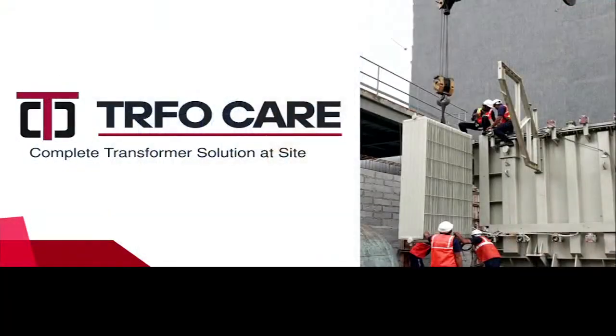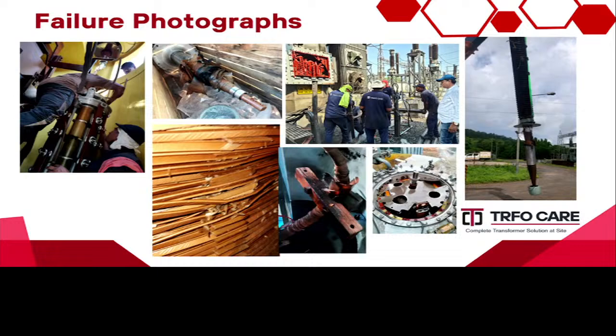So as a service provider, I will show you some pictures as well as case studies of different types of failures in the transformers, how to maintain the transformer, and, if this type of failure occurs, say DGA, some acetylene or ethylene, any key gases you find in the transformer, what should be the precautionary measure or what activity should be carried out as a part of inspection. So I am just showing you the case studies. These are the different failures.